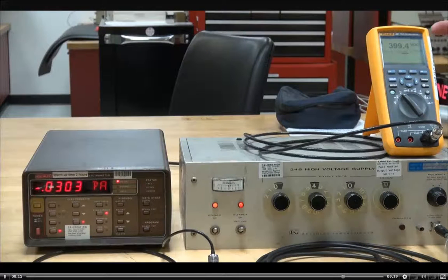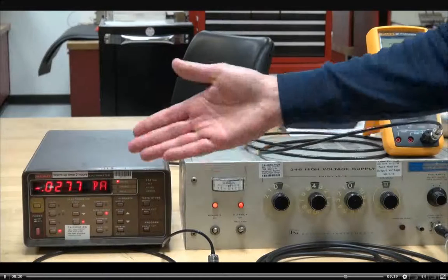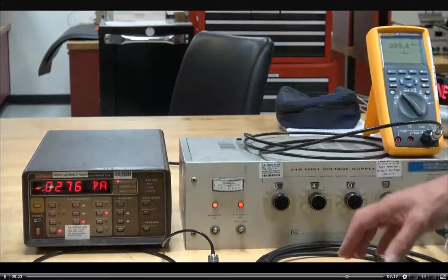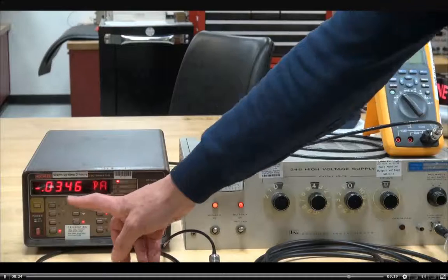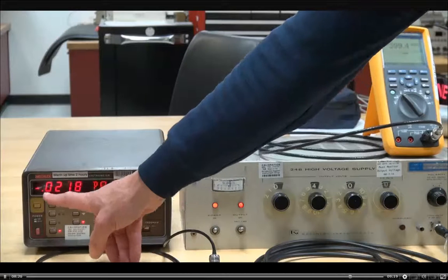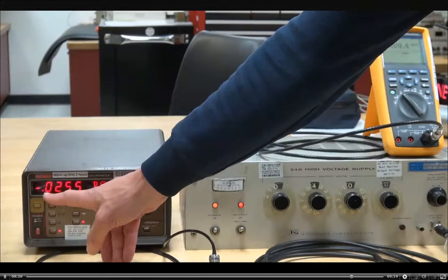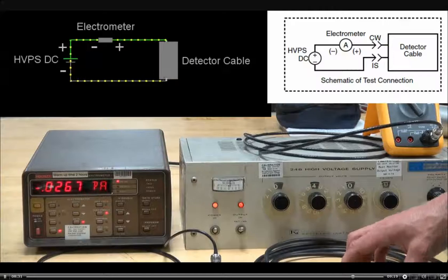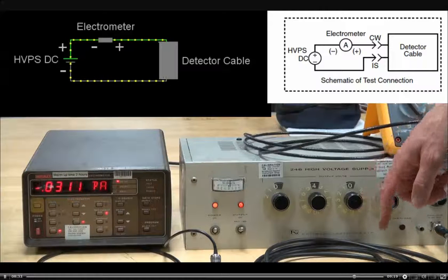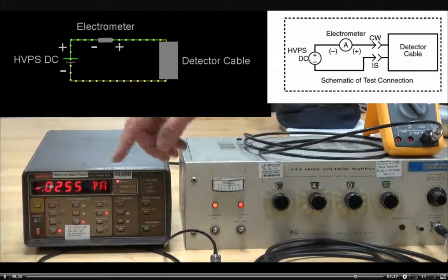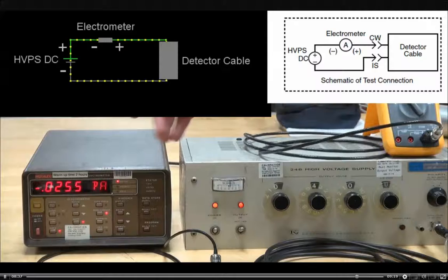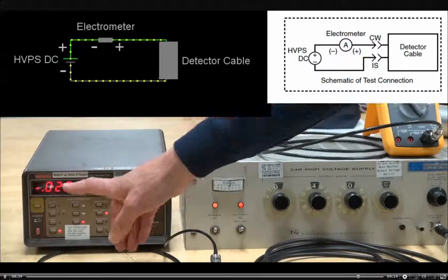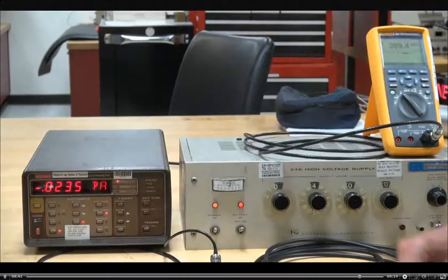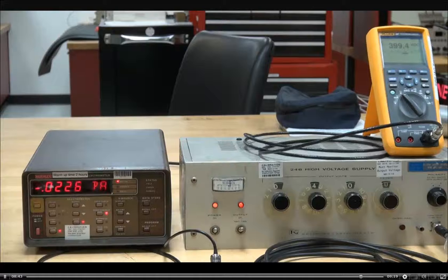Alright, now we're at the 400 volt reading, and just because of the test setup we have, we're not getting the kind of indications you would get in the plant. But notice now that our electrometer, now that we're up in voltage, is reading negative. This is to be expected. All of your readings should be negative. If you really trace out the circuit path that you have established here, the current goes through the electrometer backwards. So the reading is going to be negative. You're going to record that on your data sheet just as a positive number. Just understand that this is an expected reading.